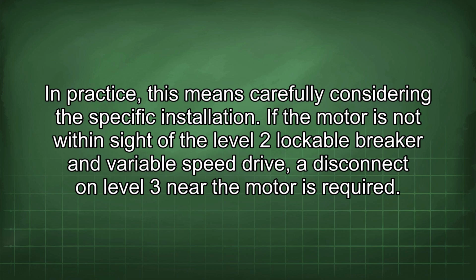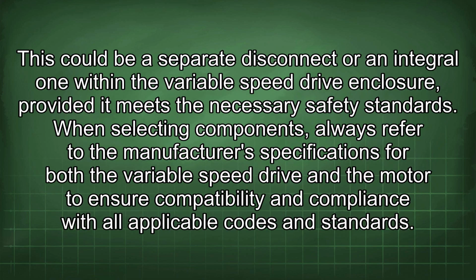If the motor is not within sight of the level 2 lockable breaker and variable speed drive, a disconnect on level 3 near the motor is required. This could be a separate disconnect or an integral one within the variable speed drive enclosure, provided it meets the necessary safety standards. When selecting components, always refer to the manufacturer's specifications for both the variable speed drive and the motor to ensure compatibility and compliance with all applicable codes and standards.